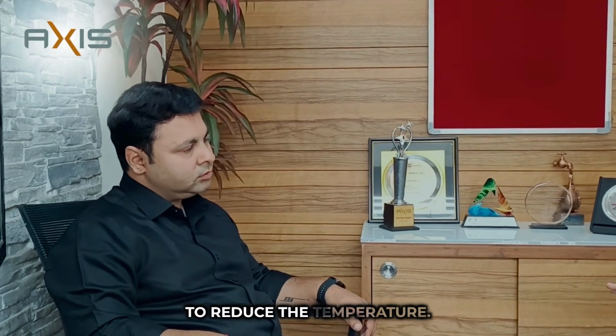The main basic components are the sample cooler, which we use to reduce the temperature, and the pressure reducing element, APRV, a variable pressure reducing element that reduces high pressure to low pressure. Then we have a back pressure regulator for pressure safety. If the APRV fails, the main sample stream pressure of 350 bar or 400 bar cannot go directly to the analyzers, so for pressure safety we use the back pressure regulator.